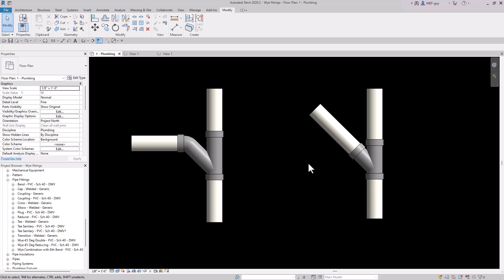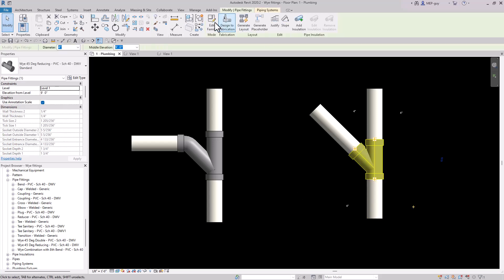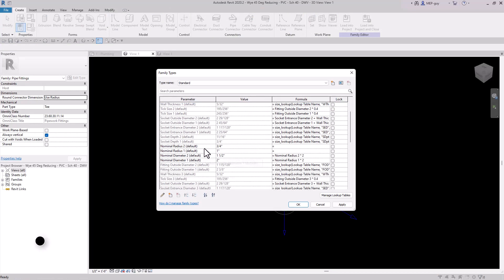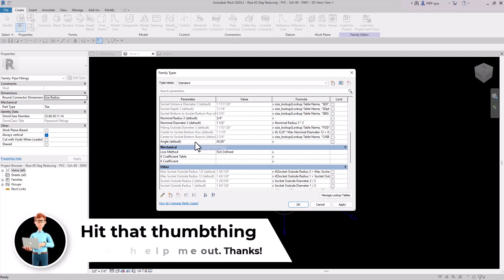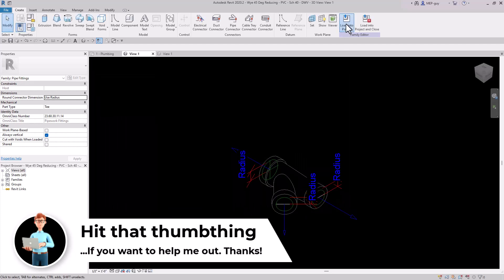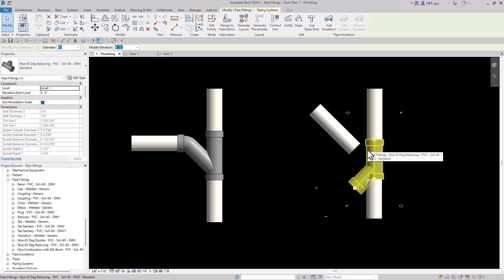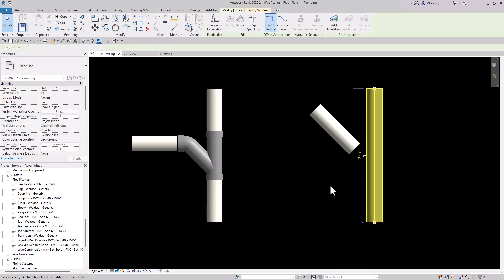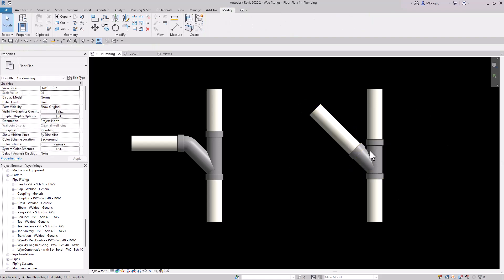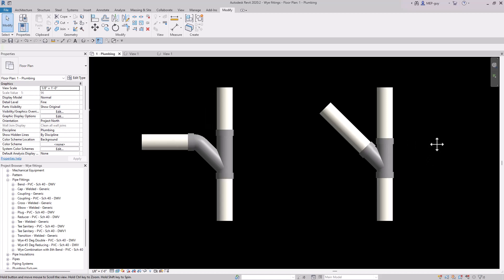We can take it one step further and lock down the Y fitting as well. Go to Edit Family, open Family Types, find the Angle parameter, click Edit Parameter, and change it from instance to type. Hit OK, load it back into the project, overwrite the existing and parameter values. Disconnect and delete the old fitting, drag the pipe, and 45 degree into it — and you can see it works perfectly. Those are the tips I would use.